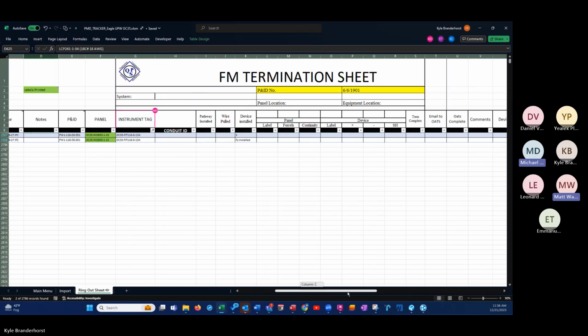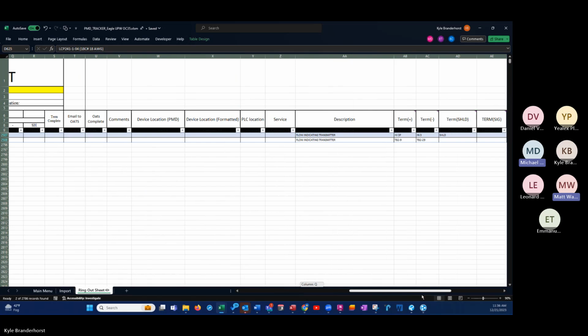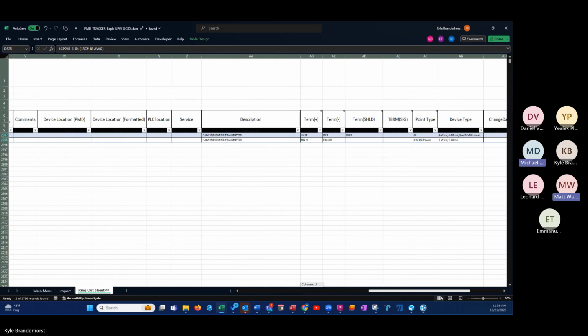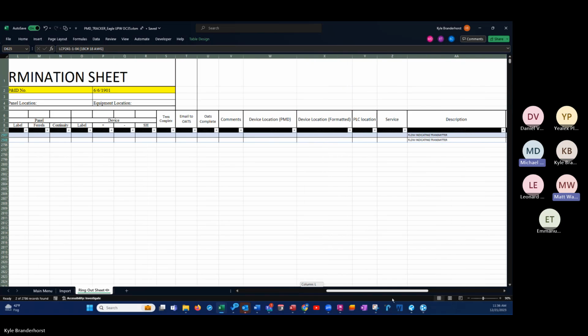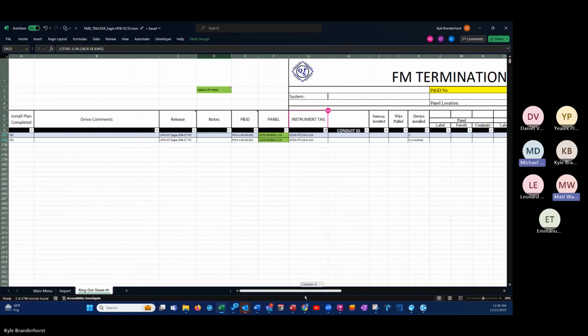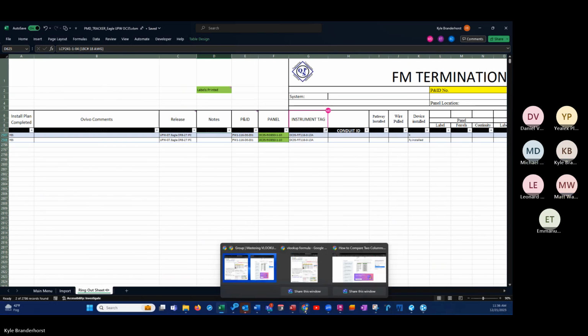Okay, well, that'll also bring me to a second question. Like that FIT, for instance, has an FY and then an FE tied to them, and the wiring actually goes from the Rio to the FY, and then from the FY to the FIT, and then they have a factory. You have 24 volts in there. FIT to the FE. Well, yes, that too.